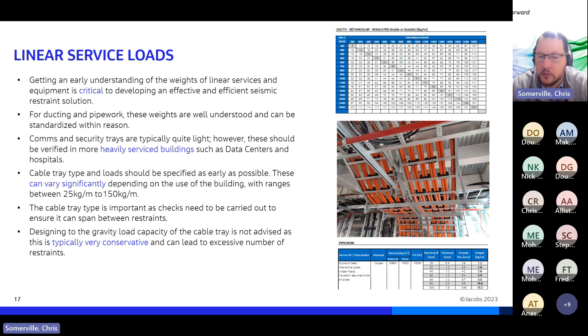We sometimes get asked to just design for the load capacity of the cable ladders - they'll give us, say, this cable ladder can support this much per meter, just design for that. But those loads are significantly higher than needed, because that's just a gravity case - the cable trays are much weaker in their other direction. So it's overly conservative to take that approach and can lead to an excessive number of restraints. I'd recommend avoiding that where possible.